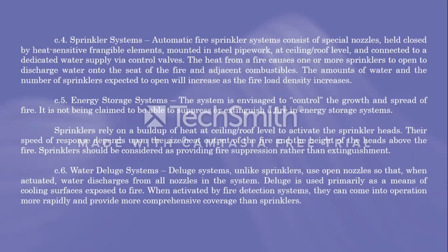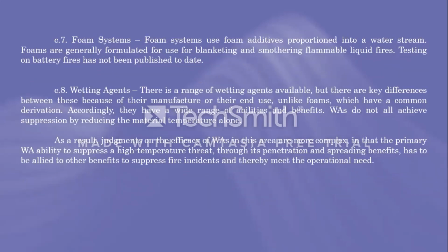Next up is the water deluge system. Deluge systems, unlike sprinklers, use open nozzles so that when actuated, water discharges from all nozzles in the system. Deluge is used primarily as a means of cooling surfaces exposed to fire. When activated by fire detection systems, they can come into operation more rapidly and provide more comprehensive coverage than sprinklers. Next up are the foam systems. Foam systems use foam additives proportioned into a water stream.